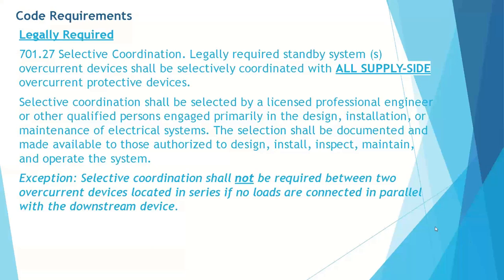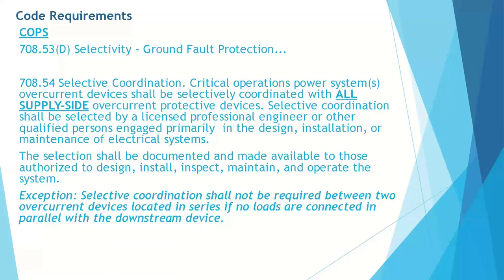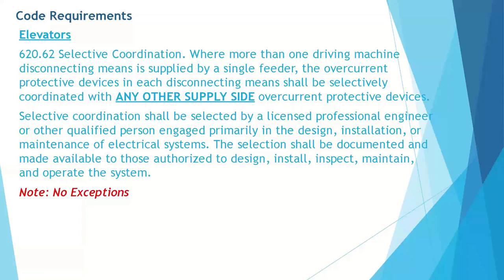In 701.27 with legally required systems, we see all supply side devices. I want to point out that the exception here states that selective coordination shall not be required between two overcurrent devices located in series with no loads connected in parallel downstream. An example of this would be an upstream feeder breaker to a downstream main breaker. Those two would be in series without any parallel loads. Or a primary side branch breaker that is feeding a transformer and then a secondary main breaker on the downstream panel. We will see an example of this later on.